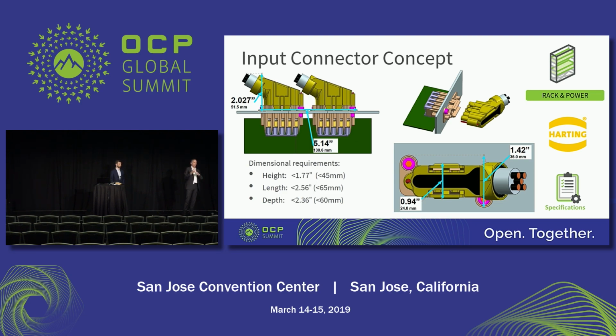So when you think about one of those big circular plugs, right? An IEC or NEMA plug. There's a specific reason for the size of those connectors, because they are really designed for being disconnected under load for like 1,000 times. And when you make smaller connectors, like the ones used on the drawer units, on the shelves, those are normally designed not for disconnection under load, but of course you have to make sure that if that happens, the connector can withstand that.